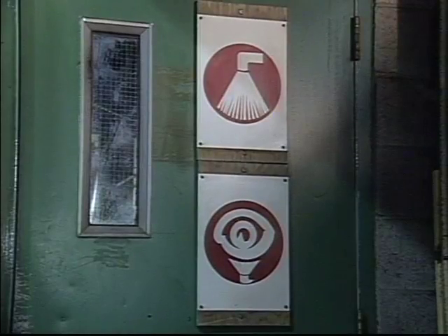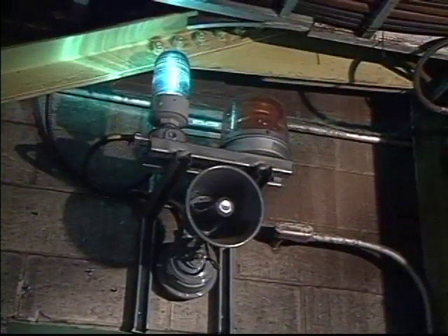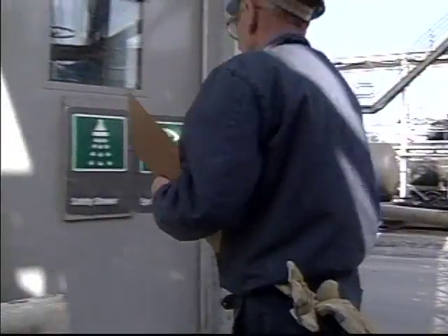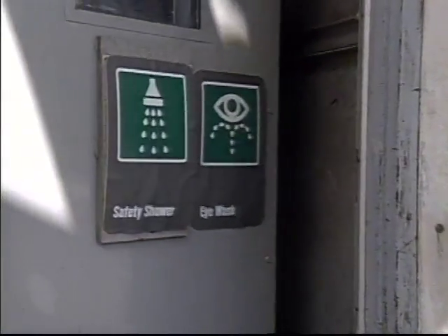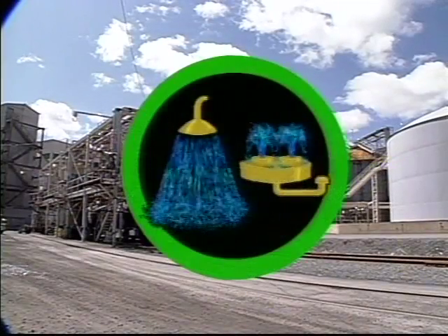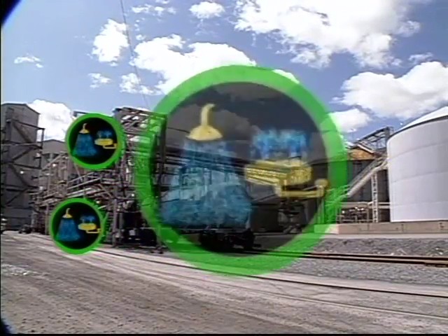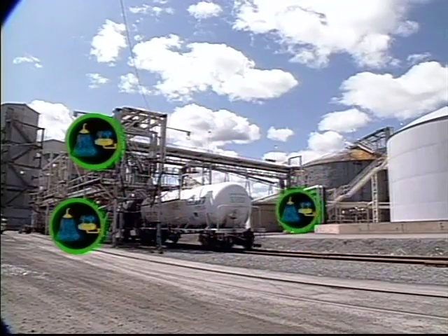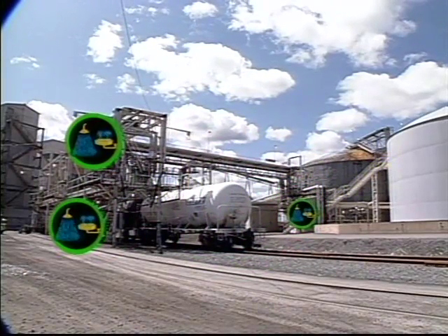Safety showers, eye wash stations, and their alarms must be located wherever acid is being handled, and they must be checked daily. At Norfolco's plants, they are located within a 10-second unobstructed walk at each level of loading areas, and also in nearby buildings, so one is always accessible, even if a large spill makes others unusable.